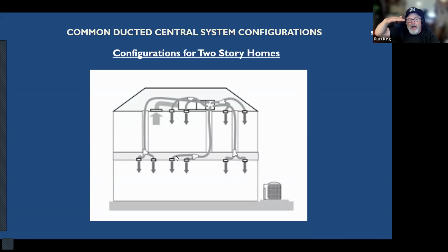Everyone else uses TJIs, which is like a wooden I-beam, and it's very, very difficult. You have to get permission from the structural engineer to go across those. So you're pretty much limited to going parallel between the floor joists and getting to where you need to put a supply register. And it can be very, very challenging. Sometimes you have to drop ceilings in hallways and closets to go underneath the floor joists. Sometimes there's beams in the way, and it's a real nightmare. All right. It's a real challenge. Hopefully architects are getting better.